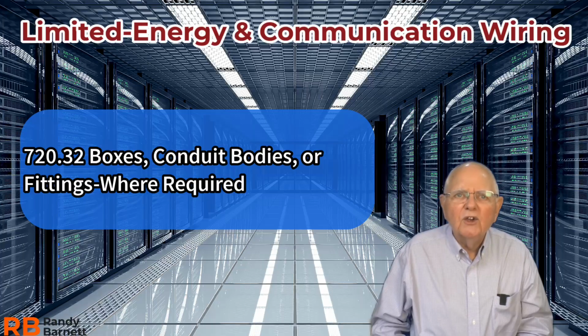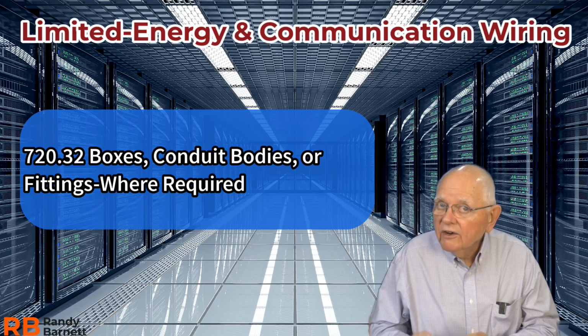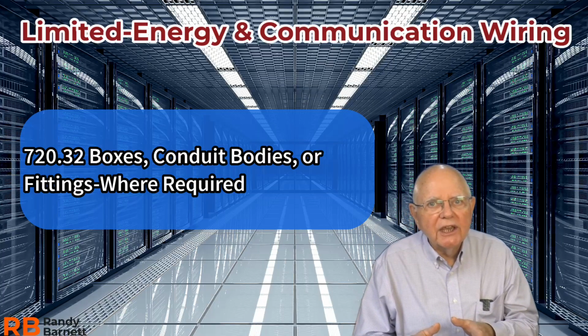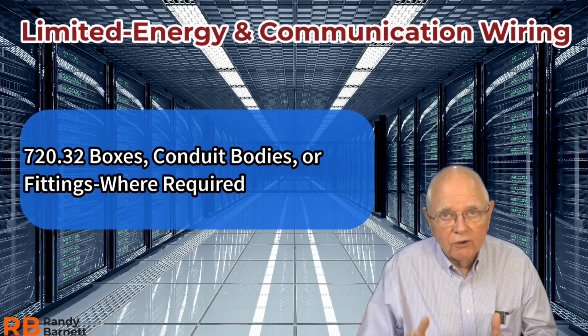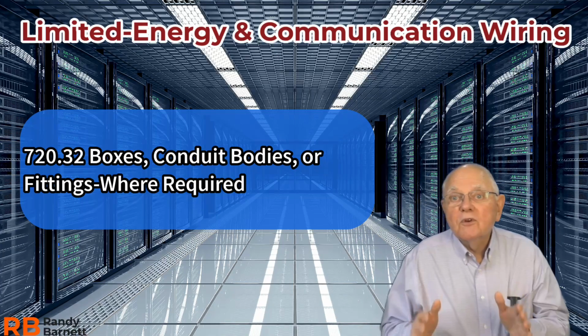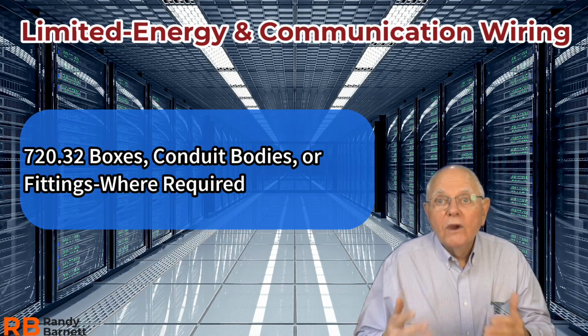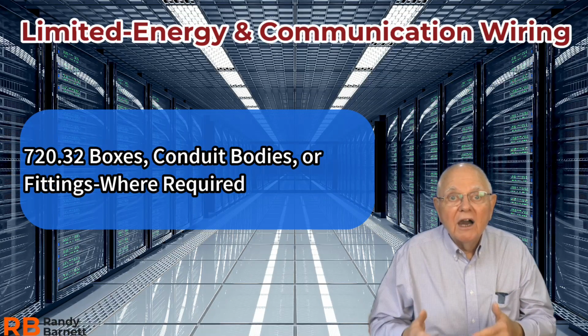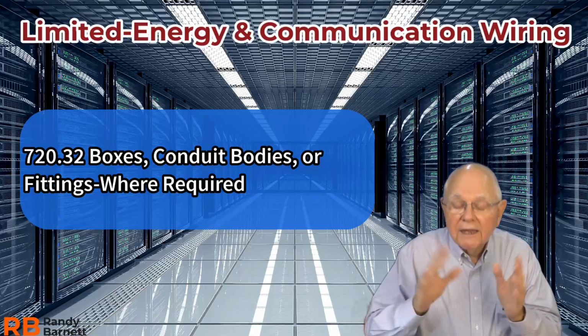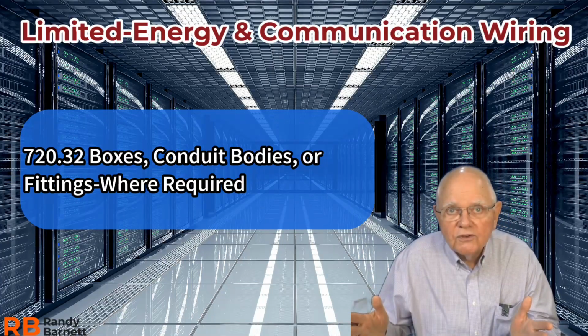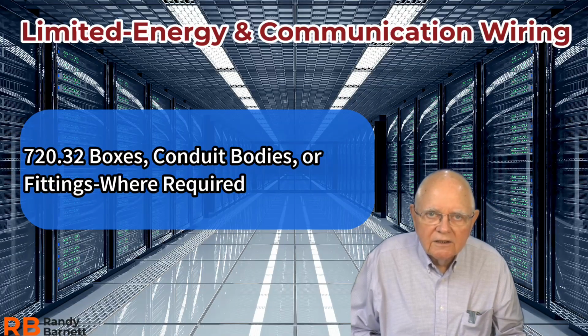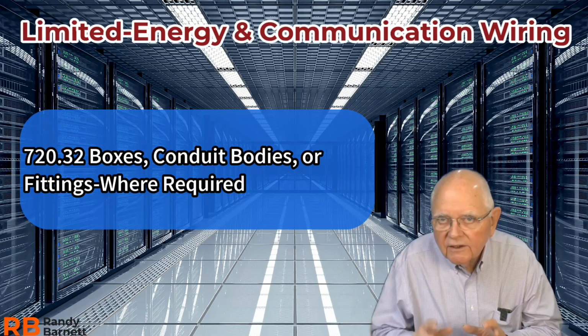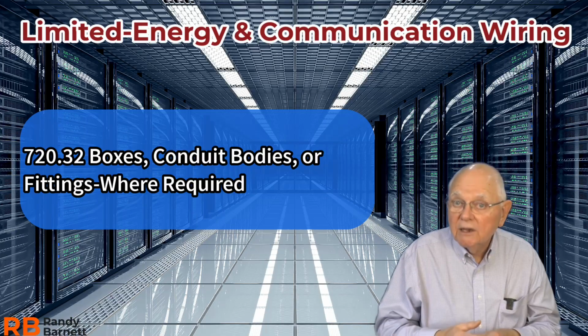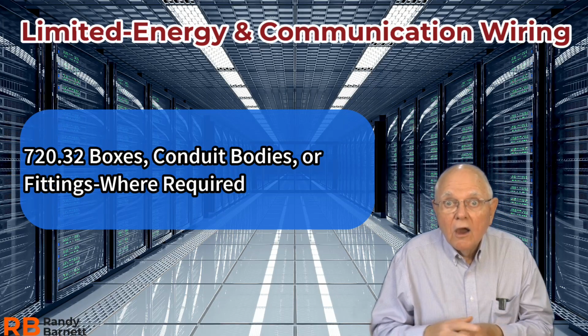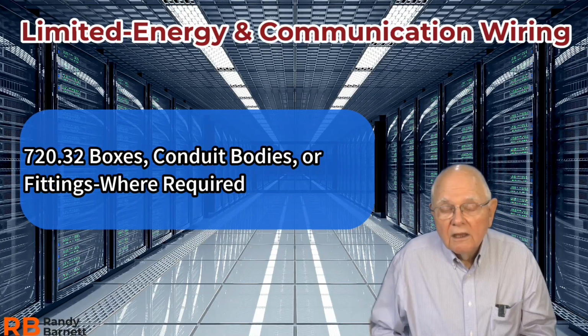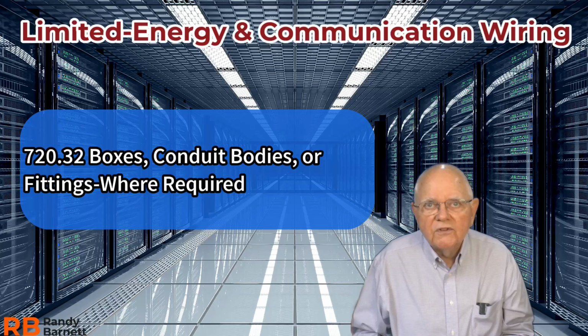720.32 is on boxes, conduit bodies, or fittings where required. Because remember, if I'm limited energy, maybe I don't always need those boxes like I do on that 480 or 240. So it gives provisions in .32 for when my cables can exit a conduit and a box not be used in order to pull through or terminate those conductors, whatever. It does require that on the end of that conduit, in that case, if I don't go into a box, I would have some type of protective fitting there, or if not the protective fitting, a seal in order to prevent damage to those cables as they come through.